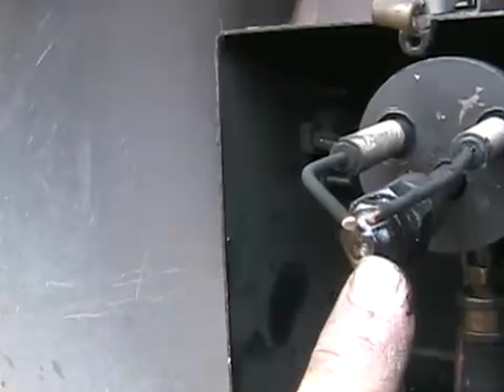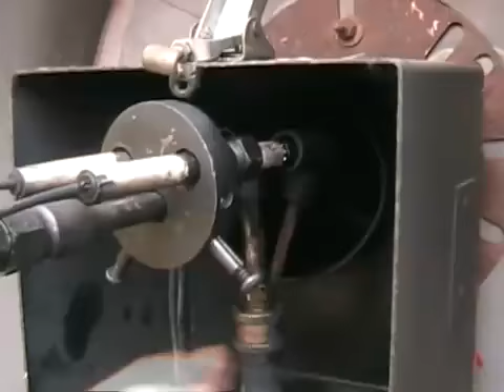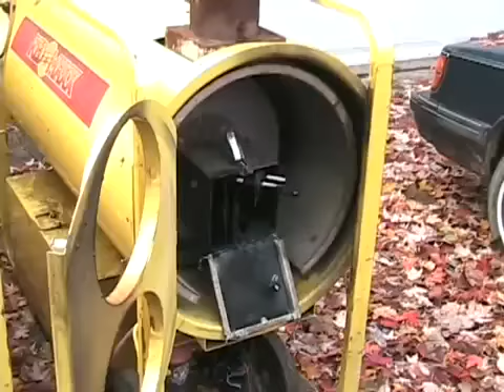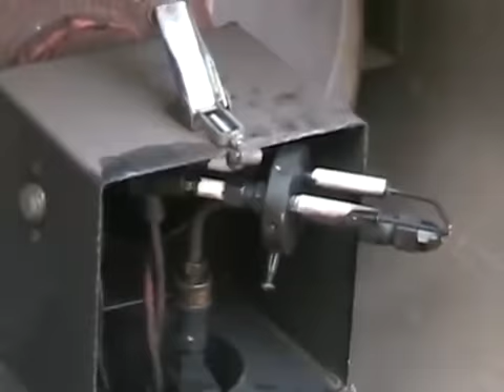When these injectors get dirty, there's a little screen behind there, and the screen collects dirt, or little tiny chunks of dirt or carbon build up there, and your little cone shape doesn't quite come out as a cone. It comes out in a funny spray pattern, which then can cause liquid fuel to end up in your combustion chamber and leak into the basement and possibly catch fire or burn really inefficiently. That part there is actually pointing around backwards. It's supposed to be pointing inside the combustion chamber, like the one on this.